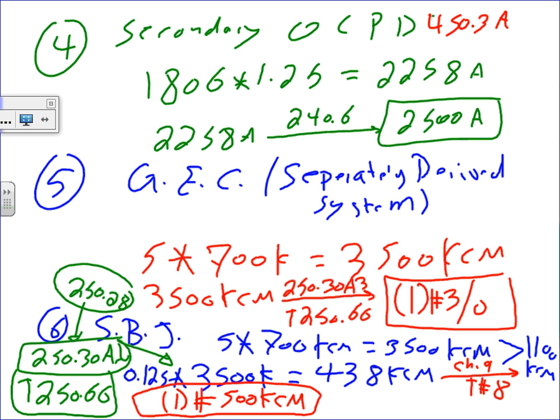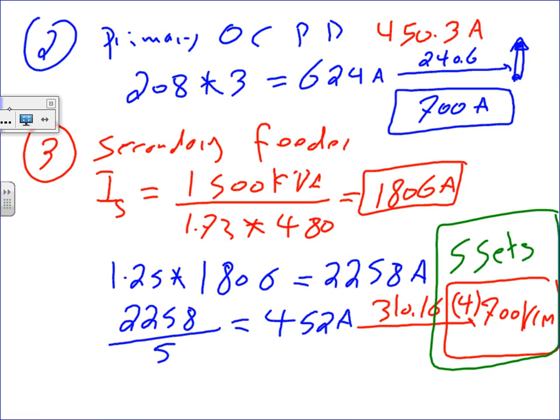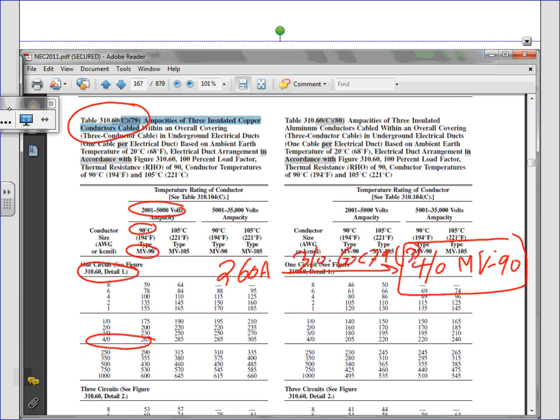The only thing I will bring to your attention, guys, really, is this table. This is a very handy table for medium voltage. Mistake number one, a lot of people, oh, I know how to size cables. You go 310.16 because we've been using it. Yes, 90% of the time you're going to be in 310.16. But that 10% of the time, you might be in this table, or any other tables. I brought you to one of them, guys. We're going to be using a few of them as we go. But really very easy. Read at the top and see.